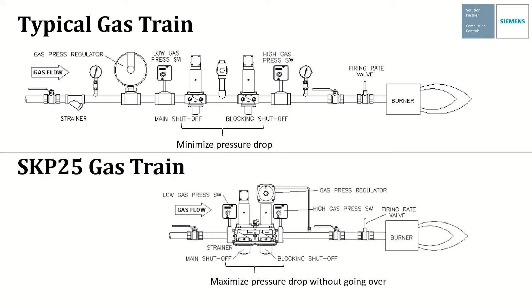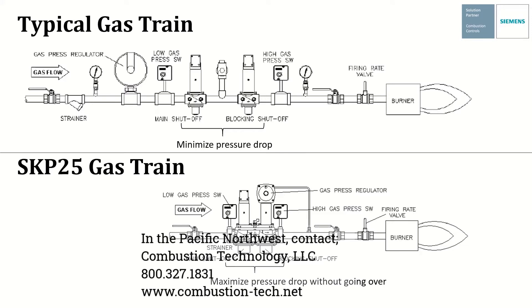The SKP25 gas train is shorter because now the regulator and the blocking shutoff valve are one component. Like sizing an orifice of a regulator, we now decrease the valve body size to maximize the pressure drop across the valve without going over. The smaller the valve body, the better the regulator function will perform.